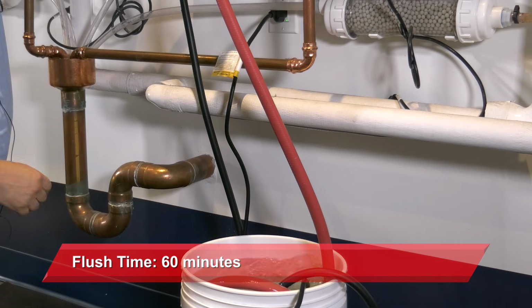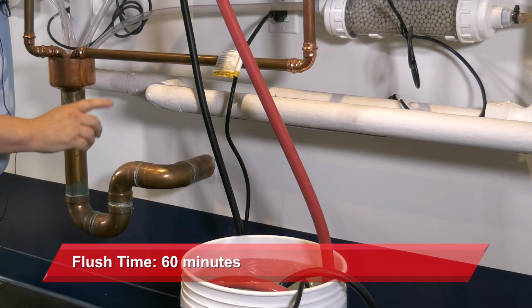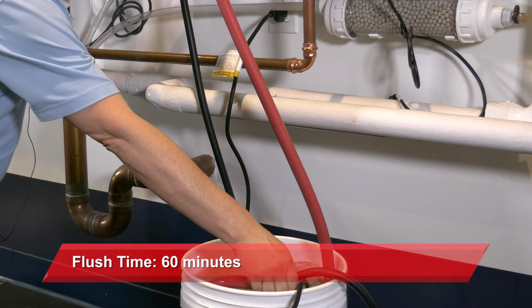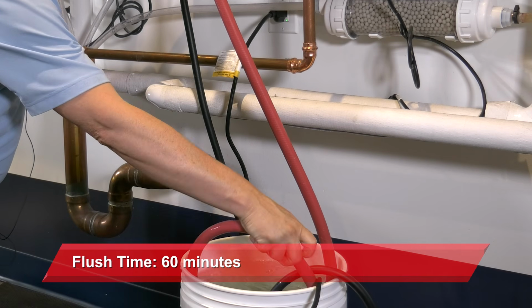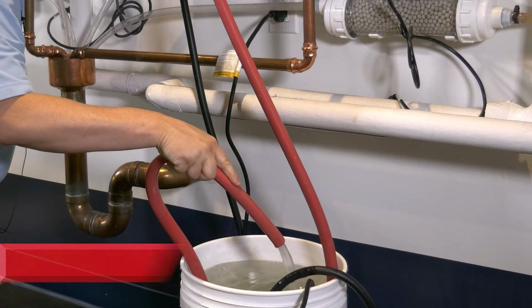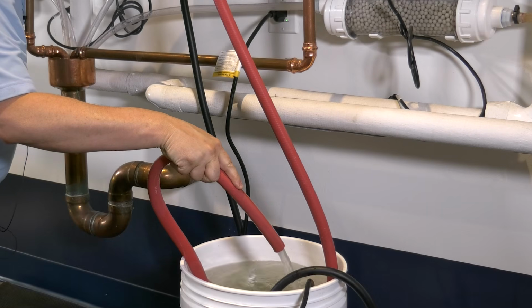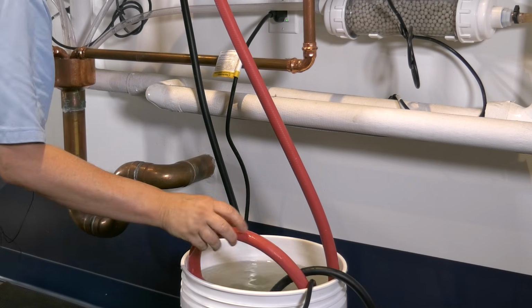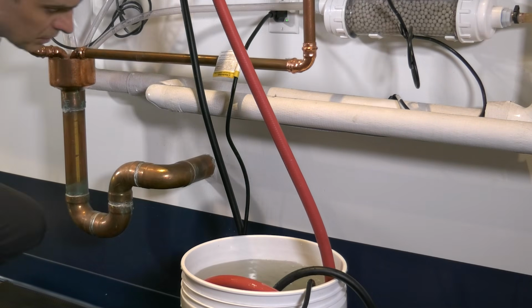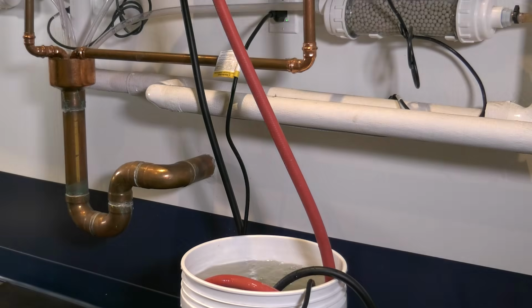Ensure the drain valves are open, your filter is in place, and plug the pump in and let the flush routine operate for about an hour. Ensure there is adequate water flowing through the flush loop. If the product does have scale buildup, the water will turn a bluish green. If the water doesn't change colors at all, like this one, you may not need to flush quite as often.